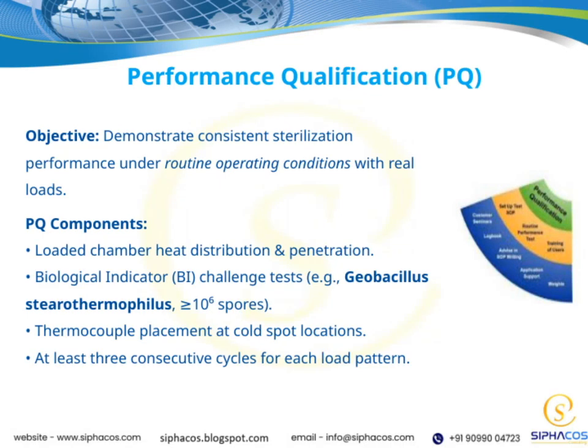The main goal here is to demonstrate that our sterilization process consistently performs as expected under routine operating conditions, and this is tested using actual loads. When we conduct PQ, we're looking at several key components. First, we need to assess the heat distribution and penetration within the loaded chamber. This ensures that every part of the load receives the proper sterilization conditions. Next, we use biological indicator challenge tests, typically with spores like Geobacillus stearothermophilus, which are highly resistant, usually at least 10 to the 6th spores, to verify sterilization efficacy.